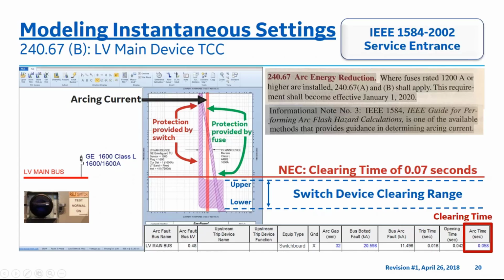The results from the Arc Flash report are as follows. In the bottom right-hand corner of the screen, it shows a clearing time of 0.058 seconds, which is the result that meets the new 2017 NEC 240.67 specification arcing current clearing time code requirement for fuses, which is the solution we are looking for. Please notice informational note number 3 in the center of the page. The IEEE 1584 reference is mentioned here as it is one of the available methods that provides guidance in terms of determining the arcing current.